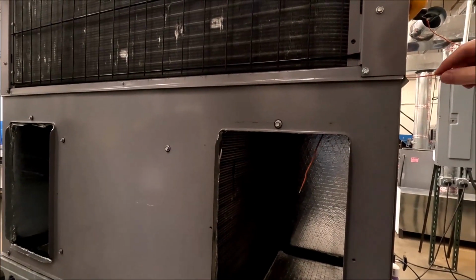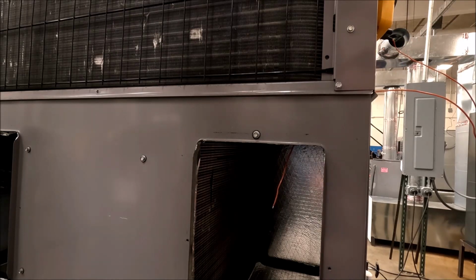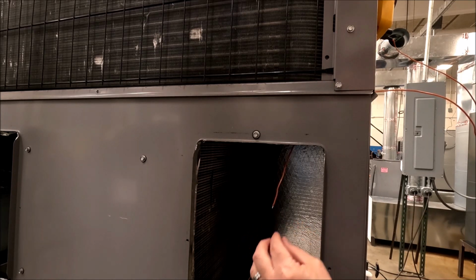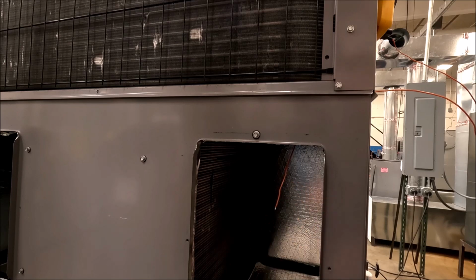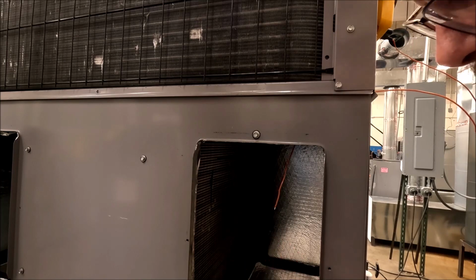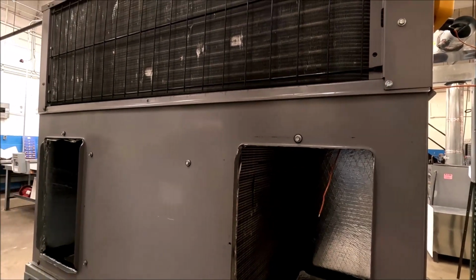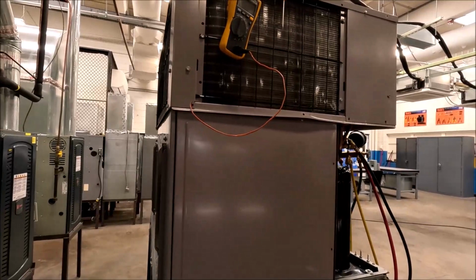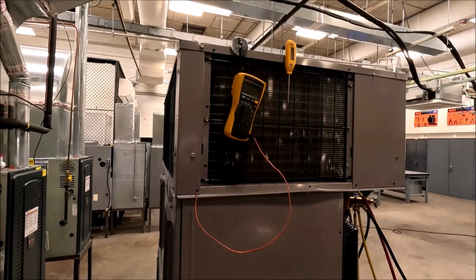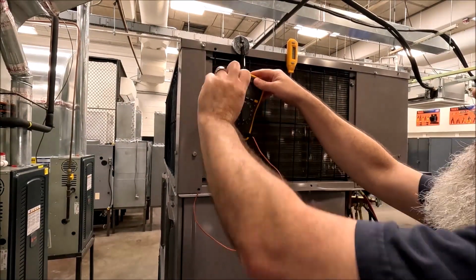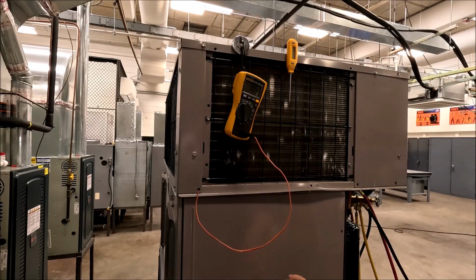If it keeps feeding in, then with the ductwork being right here, and of course you can't see it, the shroud is going to cover everything, but that little bead on that K-type would sit right there, and that air would just be coming right by it. So it's just something that I've noticed, and it works for me. So try that. Really all you're looking for is the return temperature going in the evaporator, and also the air temperature going over your condenser. So you get both those numbers that we need to start working this thing.